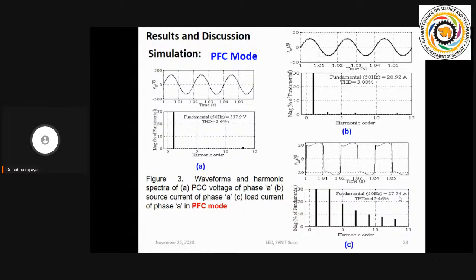After rectification, whatever DC you want to maintain, you can maintain. And see the supply side current before compensation. You are going to see 28% plus. Since we have a 4-wire system, we have three single phase circuits. In that case, the maximum you are going to get is 48%. But due to source impedance, this is going to decrease up to 40%.